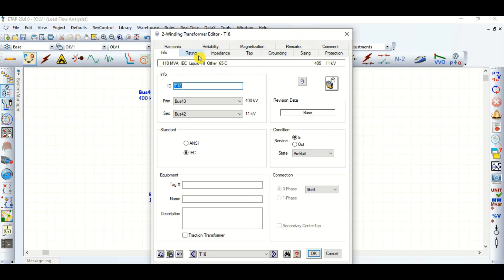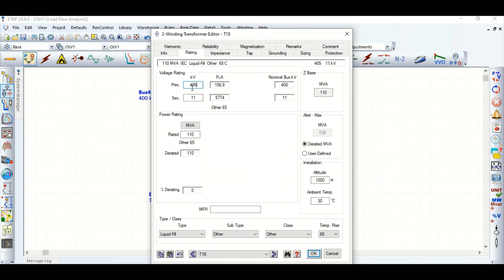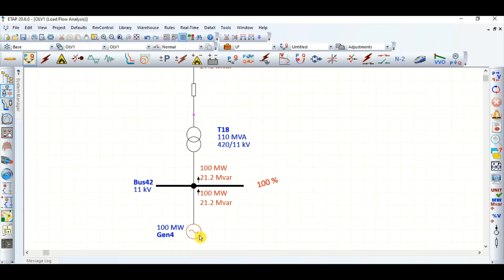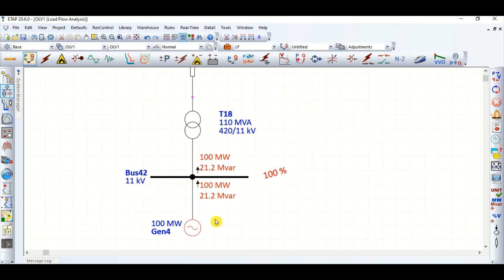We had given the wrong value earlier. 5% of 400 kV means 400 × 1.05 = 420 kV. So if the transformer primary side is 420/11 kV, let's see what happens. Previously it was minus 17 MVAR — now it is plus 21.2 MVAR.